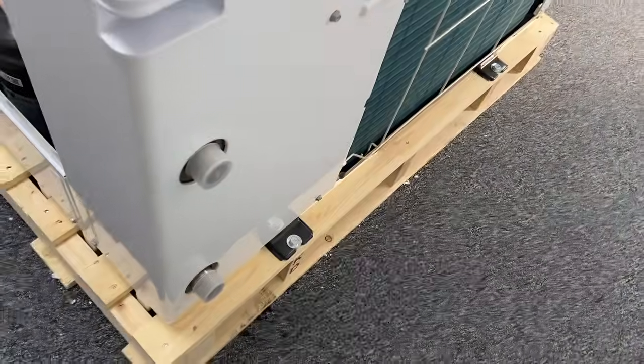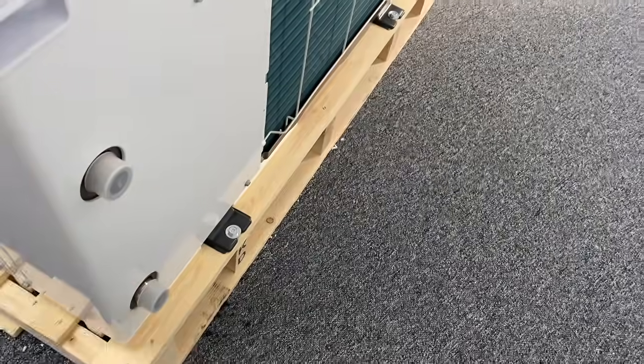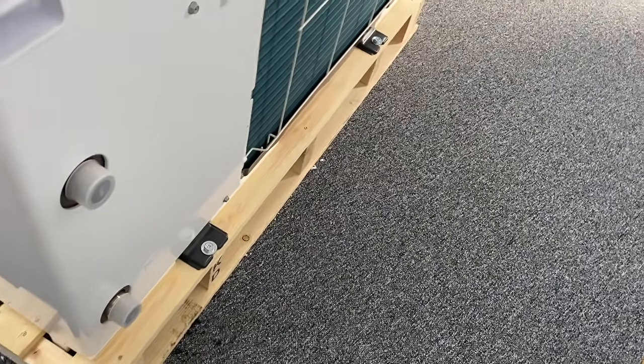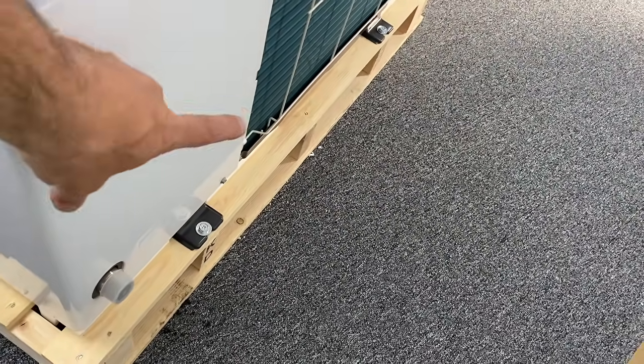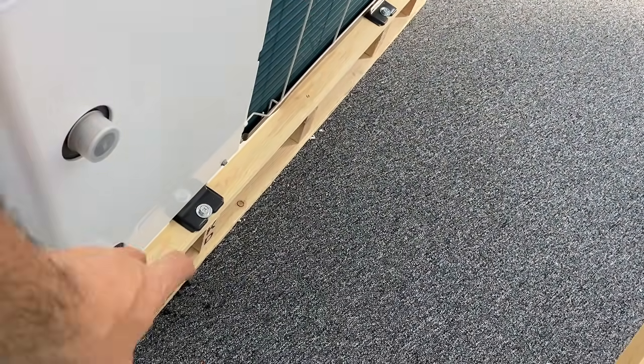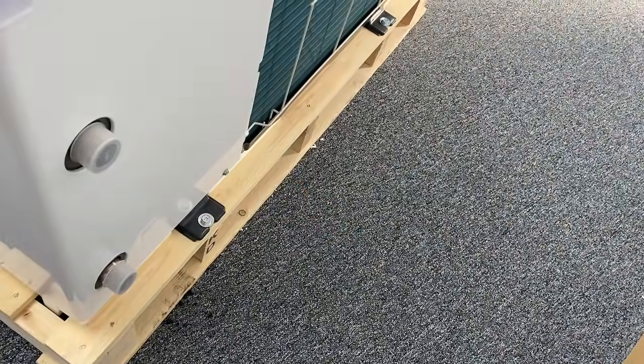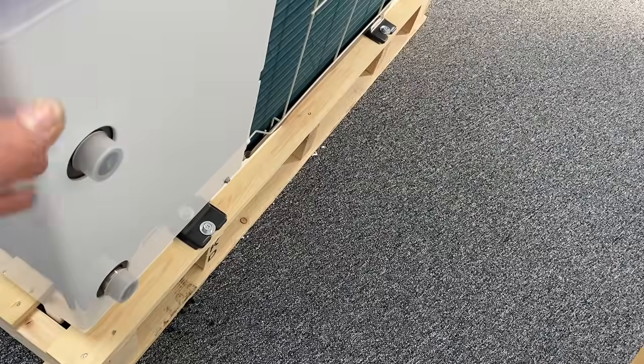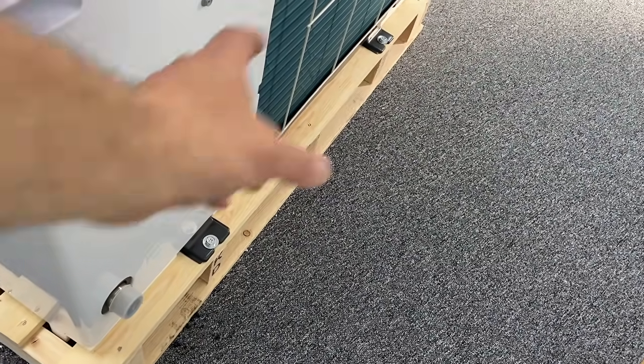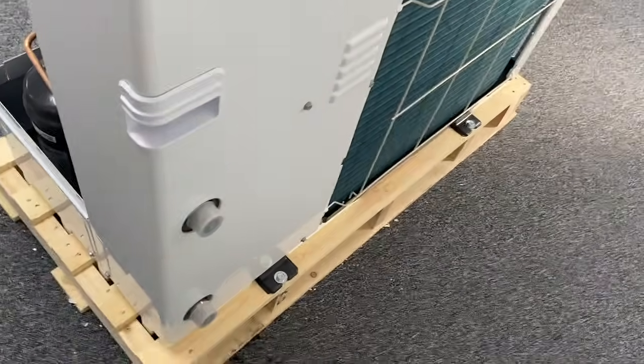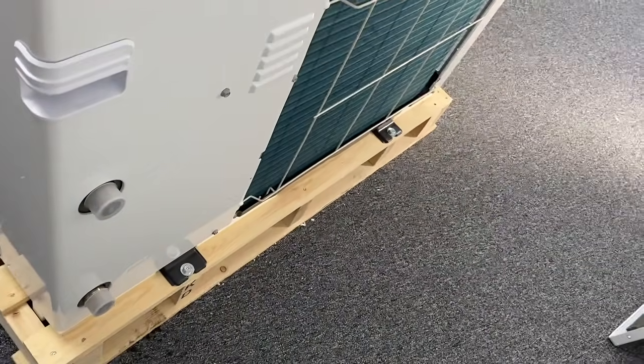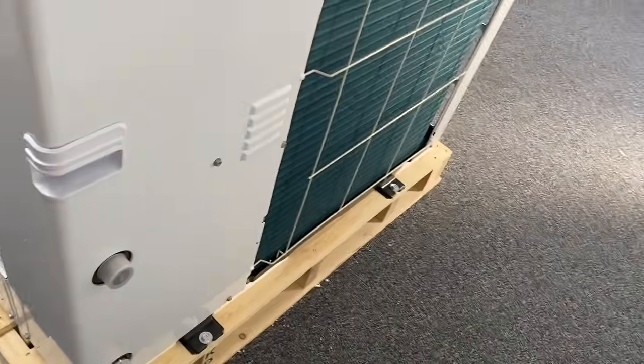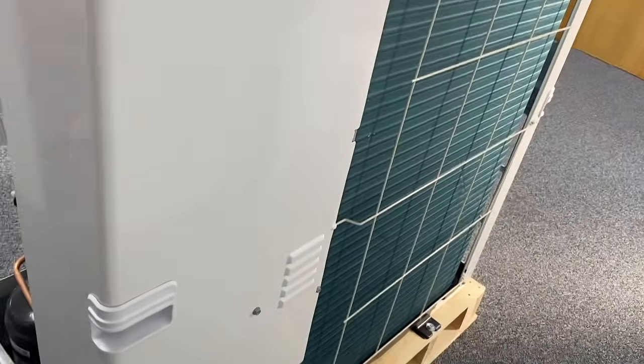The connections for the hot water, or the primaries as we call them, are simple: here and here. They will come with flexible hoses, or you order them with the heat pump. We tend to normally go for ones that have got elbowed flexes on them, purely because we end up putting this very close to a wall generally, and then we have somewhere that we can connect onto. We'll bring our primaries out and we have to make sure everything's very well insulated. But the connection on the outside is very simple.